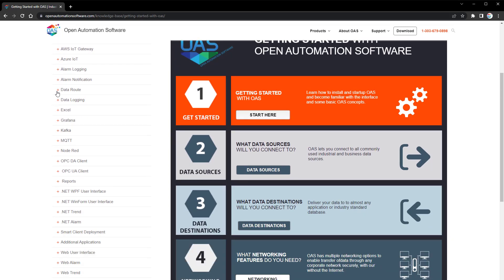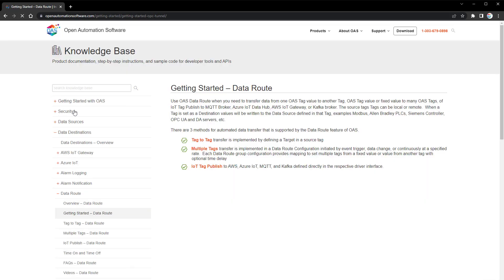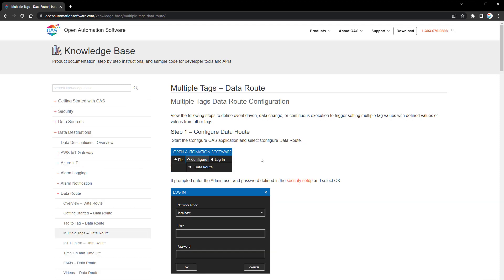Under Data Destinations, we have Data Route. In the Getting Started Data Route section, we'll see three descriptions of each method. There's the tag-to-tag data transfer, using the source tag and target tag of an OAS tag to write to another tag. There's also the IoT Publish feature that works with Azure, AWS, MQTT, and Kafka to publish data using the driver interface built into OAS. We're going to review the multiple tag transfer feature, which can be triggered based upon an event, a data change, or executed continuously.